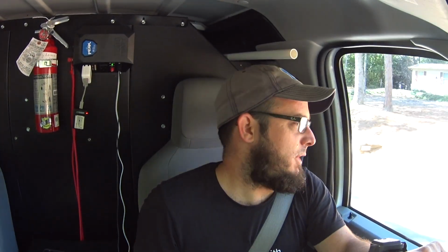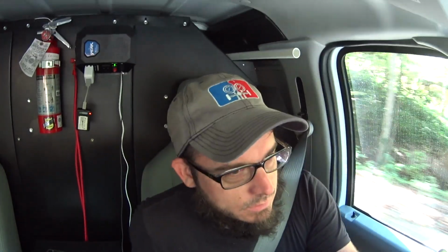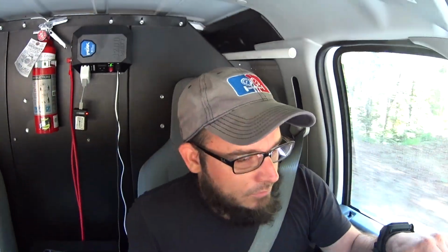As you can imagine, when 7 air handlers or 7 coils have been replaced on the system, it's had at least 7 evacuations or pseudo evacuations. So I'm going to let that run. I've got a couple of service calls that I need to get taken care of, and rather than sit there and babysit it, I'm just going to let it suck. And then we'll come back after we get these service calls.